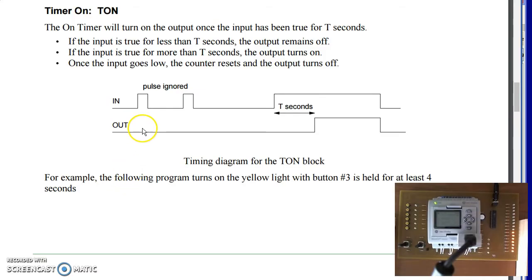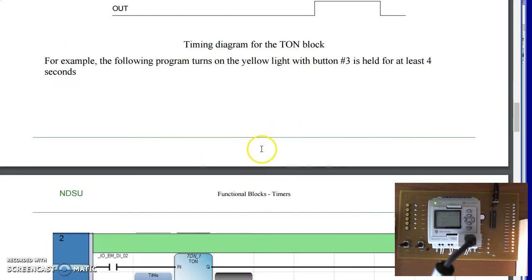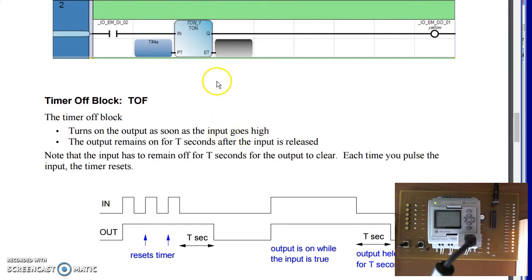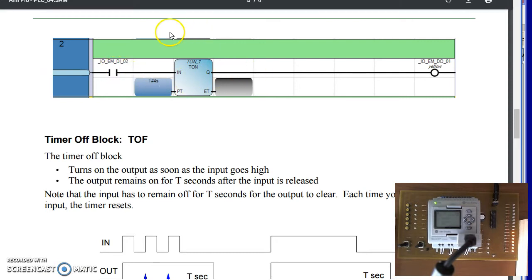Next is the T on block. T on will leave the output off unless the input is held on for T on seconds. Here's the notation. This means the input has to be held for 4 seconds for the output to be turned on.